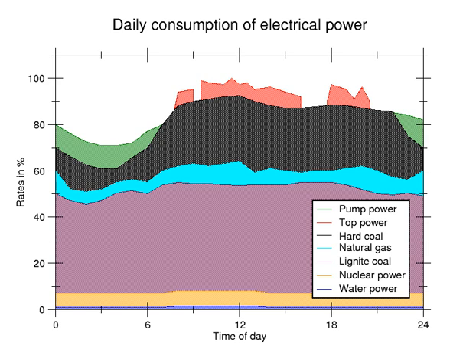There is therefore a physical requirement for a controlling agency — the transmission system operator — to coordinate the dispatch of generating units to meet the expected demand of the system across the transmission grid. If there is a mismatch between supply and demand, the generators speed up or slow down causing the system frequency, either 50 or 60 hertz, to increase or decrease. If the frequency falls outside a predetermined range, the system operator will act to add or remove either generation or load. The proportion of electricity lost in transmission and the level of congestion on any particular branch of the network will influence the economic dispatch of the generation units.